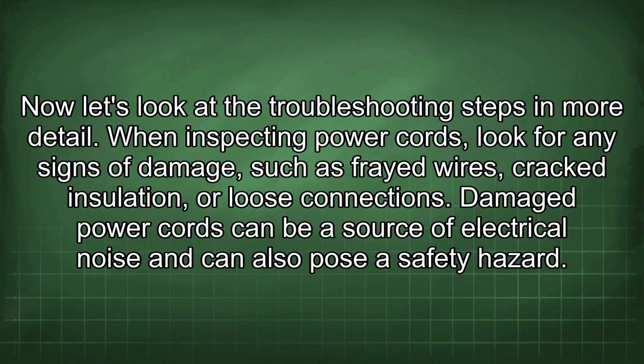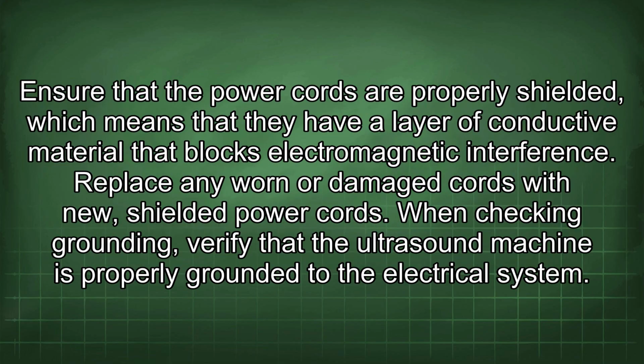When inspecting power cords, look for any signs of damage, such as frayed wires, cracked insulation, or loose connections. Damaged power cords can be a source of electrical noise and can also pose a safety hazard. Ensure that the power cords are properly shielded, which means that they have a layer of conductive material that blocks electromagnetic interference. Replace any worn or damaged cords with new shielded power cords.